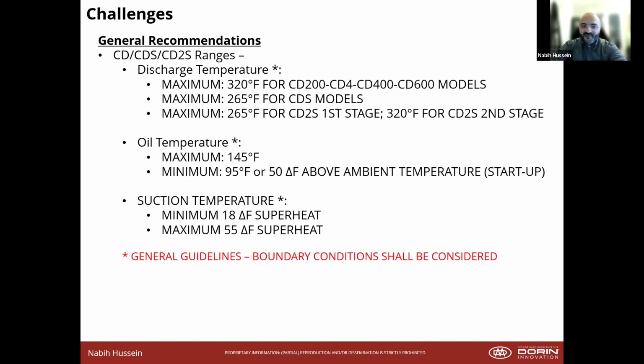Here's some general recommendations we have. They apply to our ranges, but it could be any of the other ones. We would really say stick to boundary conditions when you're looking at compressor sizing, but you're looking at 320 degrees as your discharge temperature, making sure your oil never exceeds 145 degrees, and that you always have superheat at your suction. So the quickest way to destroy a compressor is to have liquid enter into it. And that's why we have that 18 degrees of superheat, but there's also the maximum of 55.